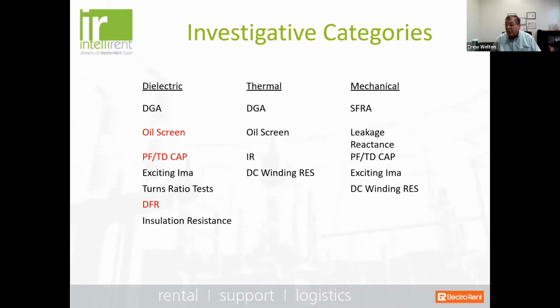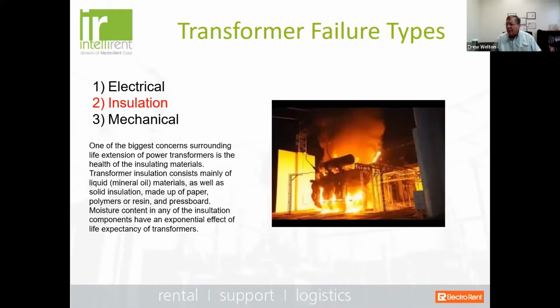For dielectric, we're talking about the insulation, and we typically start with an oil screen or a DGA analysis. We do things like power factor or tangent delta, as they say over in Europe. And then another diagnostic test we want to talk about today is dielectric frequency response. And you can see that whether you have a mechanical, thermal, or dielectric category in which you're going to investigate the health of the transformer, some of them do overlap in certain areas. So, there are basically three types of transformer failures. You have electrical failures, you have mechanical failures, and then what we're going to talk about today are insulation failures.